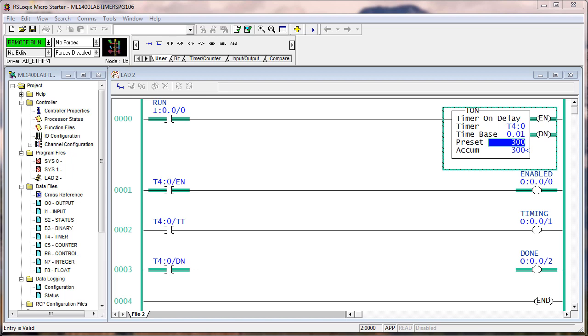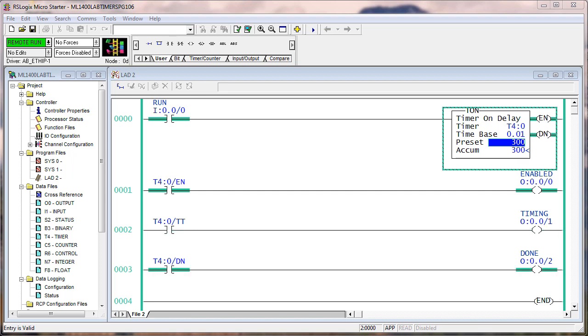The timer stays done until you either reset it or turn off input zero, which clears the entire data type. The true execution of the TON instruction enables the timer data type, starts counting units of time, turns on the timer timing bit, and when the accumulate equals the preset, turns off the timer timing bit and the done bit comes on. The false execution is when the rung goes false — it clears the accumulate value and all of the control bits go back to zero.